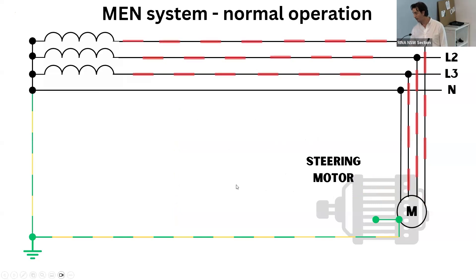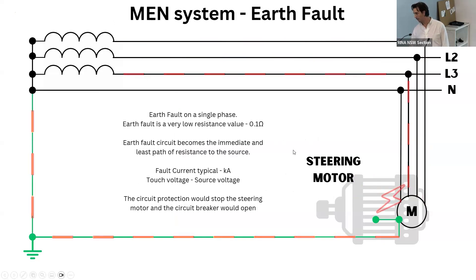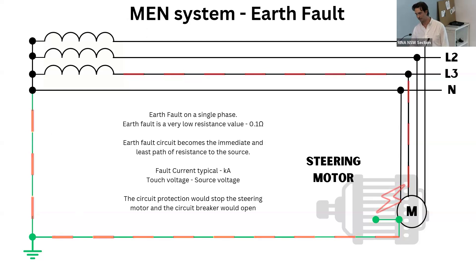Moving on to the MEN system — it would look something like this, with current flowing. Sometimes there might be current on the neutral depending on the type of motor. If you have an Earth fault, you're going to have a very large current flowing through your Earth back to your source. The circuit breaker would open and your plant is going to stop. You're going to have a very large fault current in the kilo-amps — and that's the main difference.